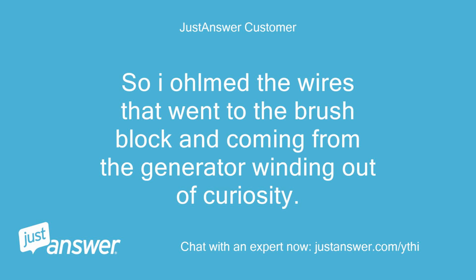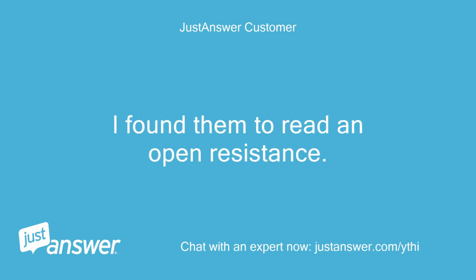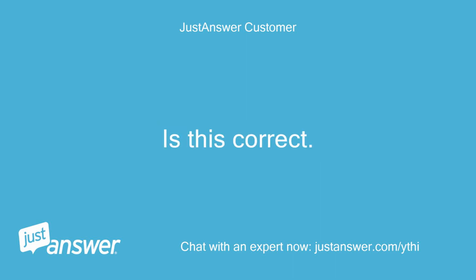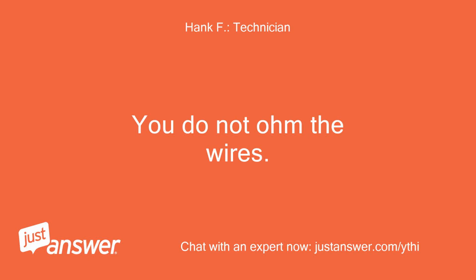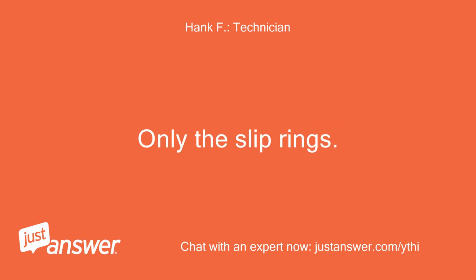So I ohmed the wires that went to the brush block and coming from the generator winding out of curiosity. I found them to read an open resistance. Is this correct? You do not ohm the wires. Only the slip rings.